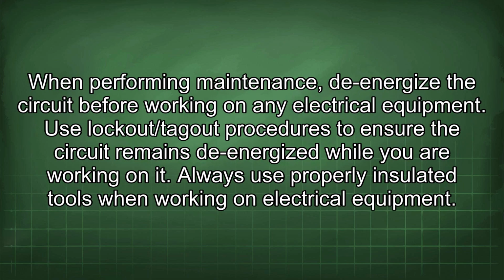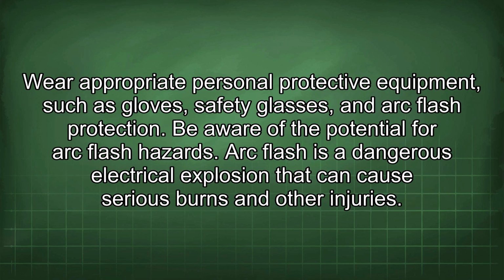When performing maintenance, de-energize the circuit before working on any electrical equipment. Use lockout/tagout procedures to ensure the circuit remains de-energized while you are working on it. Always use properly insulated tools when working on electrical equipment. Wear appropriate personal protective equipment such as gloves, safety glasses, and arc flash protection.